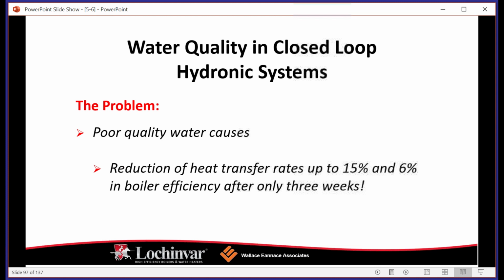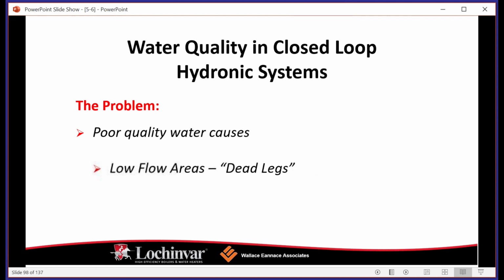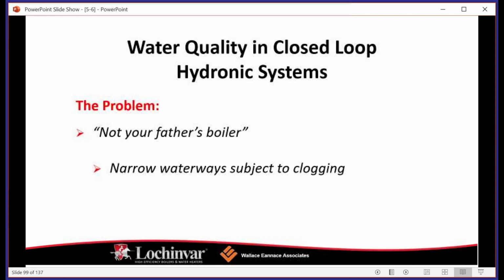And again, remember that this is a closed loop system, right? So the boiler should never have any more or less water than it did on the day you started it up. If the water fill, the water meter is running into the boiler, that means you have a leak, right?